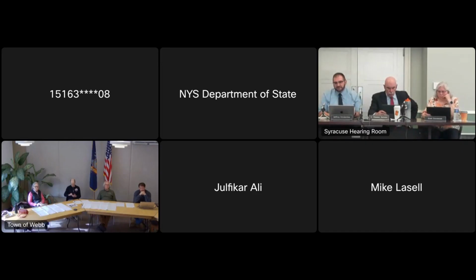We recognize that these are old structures that have stairways that find their way through buildings. There are multiple apartment units. So what we typically do, in looking at your pictures and your structure, is require smoke alarms and heat detection devices that have to be hardwired in the structure, and they have to be installed as directed by the fire code official. Two smoke alarm devices get provided in the cellar, and a smoke alarm shall be provided on every landing on the front and the exit stairways. And this will all be in writing for you as we go through this.